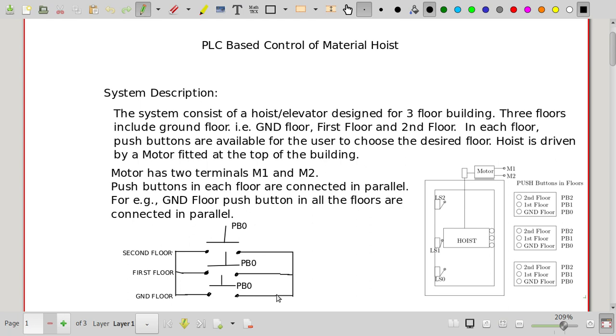To indicate the presence of the hoist on a specific floor, limit switches are placed at the back of the hoist. A limit switch is a mechanically actuated switch — there is a spring-like setup. When the hoist slides over the limit switch, the spring setup closes the switch. Once the hoist has moved beyond the limit switch, it opens again due to the spring arrangement.